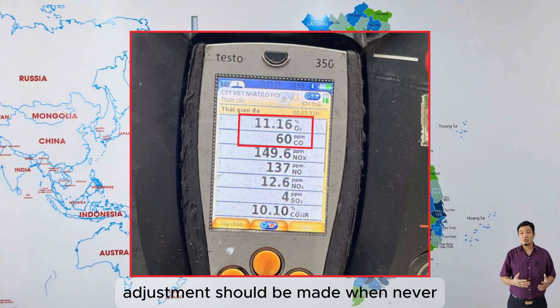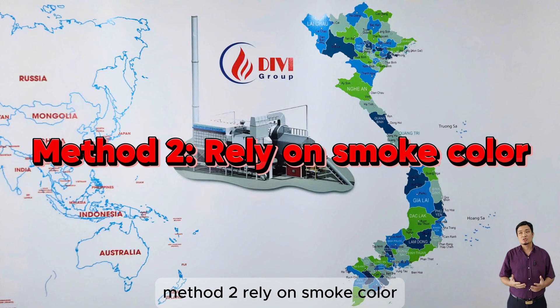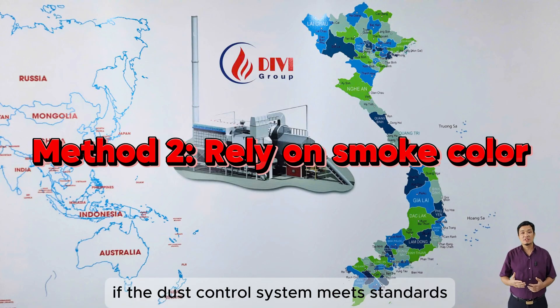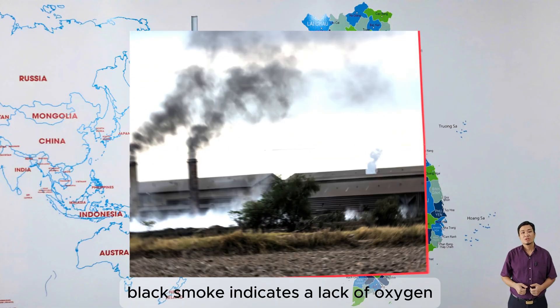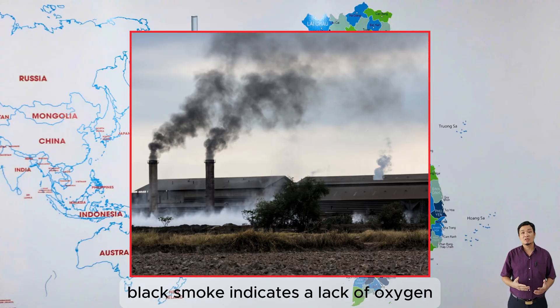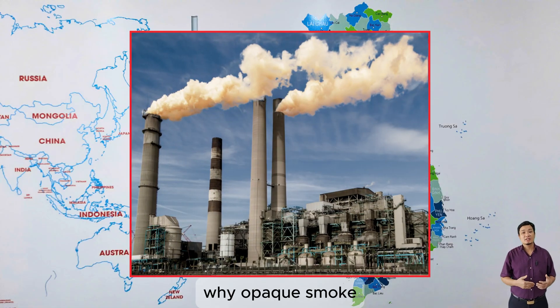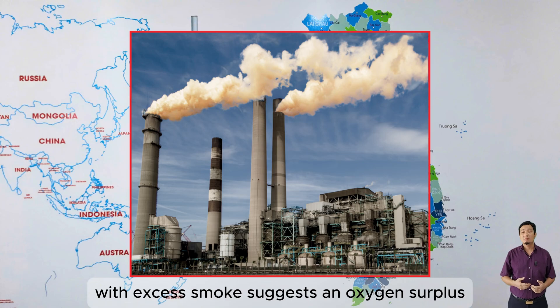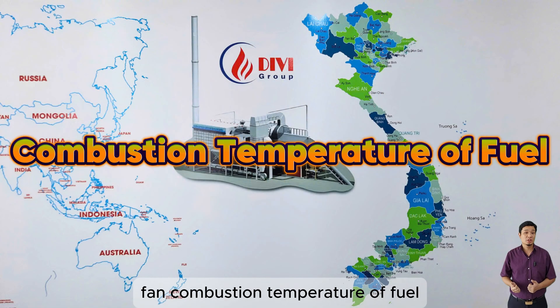Adjustments should be made whenever there is a change in fuel. Method 2: rely on smoke color. This method only applies if the dust control system meets standards and the smoke color is due to CO. Black smoke indicates a lack of oxygen, requiring an increase in the air supply fan. White opaque smoke suggests an oxygen surplus, necessitating a decrease in the air supply fan.